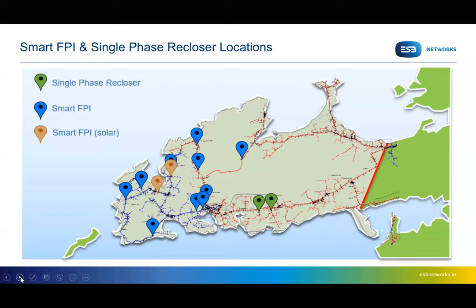Now, trials of recloser devices on single-phase circuits have previously taken place elsewhere on our networks in the country. And they showed that well over 90% of the faults are often transient in nature, caused by things like bird strikes or branches tipping against the lines.